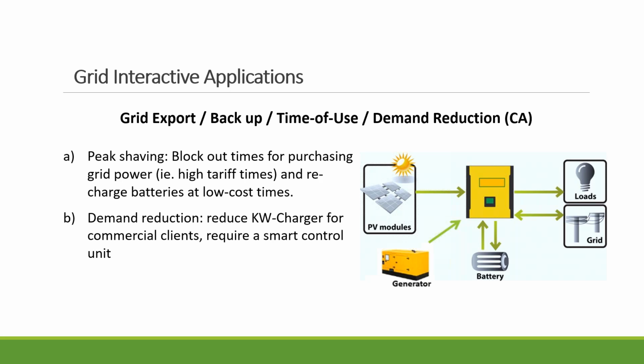Typically, if you need to use the grid power to charge the battery, it will happen when the tariff rate is low. Now, for commercial customers, there is the kW charge. The utility measures the kW every 15 minutes. If you have a hybrid inverter and a battery, and add a smart control unit to it, then before that 15 minute interval comes in, the control unit can turn on the energy storage to reduce your kW charge. And for some areas, that's a significant savings.